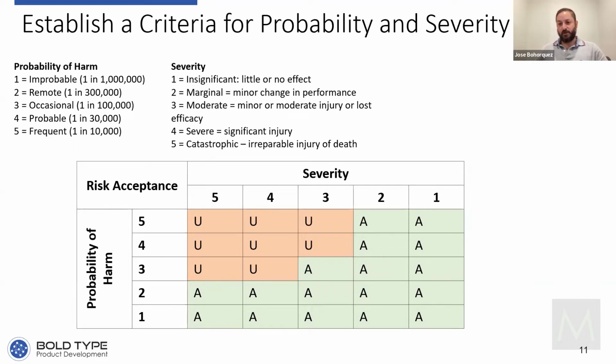You have a responsibility to go back, evaluate what that does to your risk analysis, and then implement risk controls, and even, in the extreme case, potentially this could drive a recall. If this is something that's really putting patients at risk. Most of the time, it's not quite that severe, but it is an ongoing process that continues.